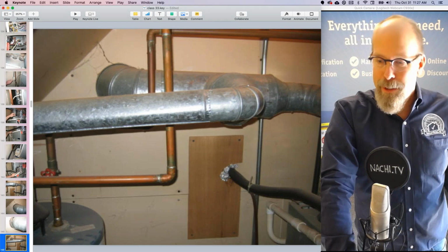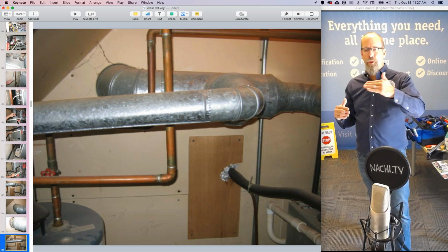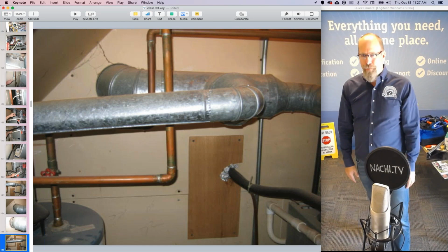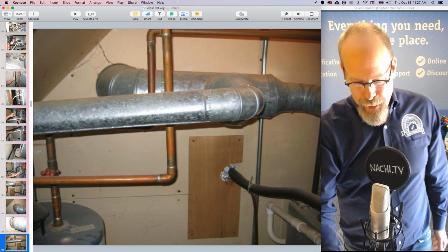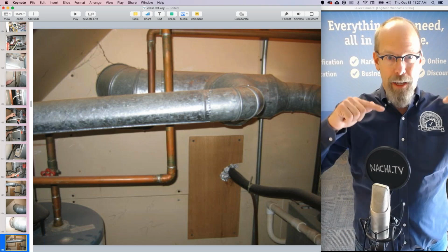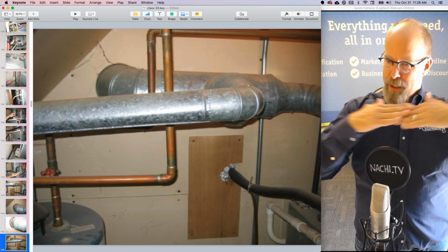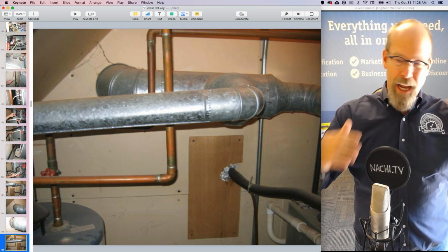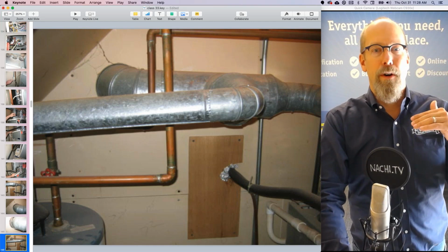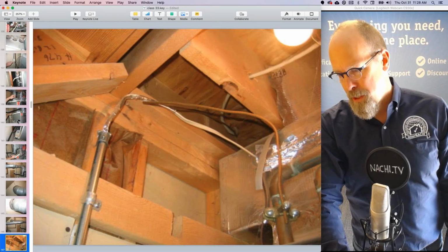And I'm kind of concerned about the slope too. That furnace there and that flue of the hot water tank coming in at a weird angle because the pipes got in the way. It's kind of flat. So I've got two concerns now. I've got the rusted collar at the top, poor flashing around the chimney stack at the top, remember in the webinar? And then I've got this vent connector pipe that's almost level, and I have an inadequate clearance from combustible materials. I've got really great reasons for recommending HVAC service and cleaning and further evaluation.